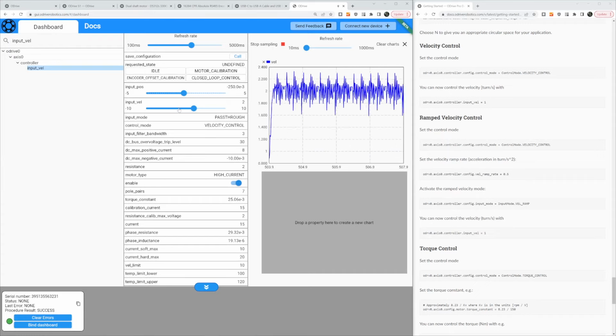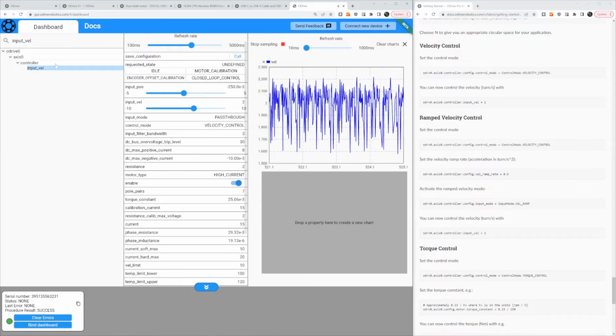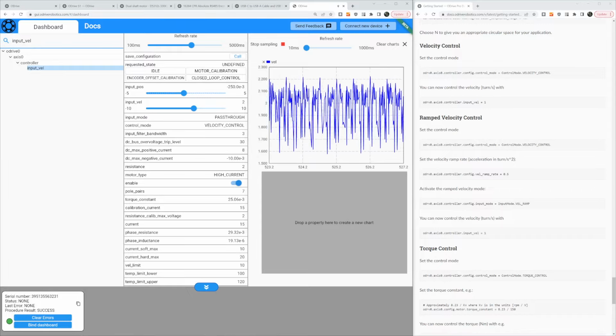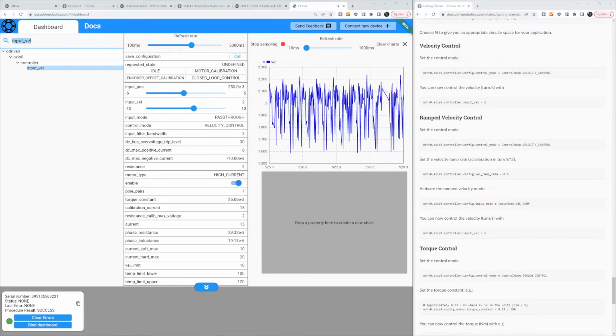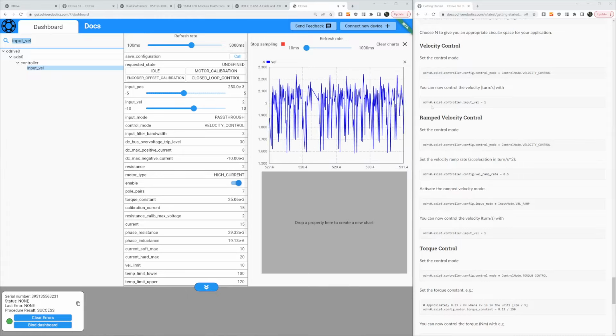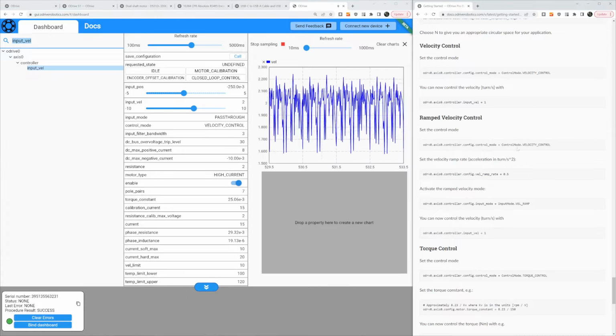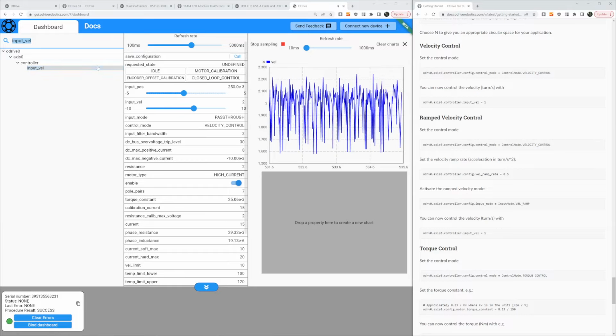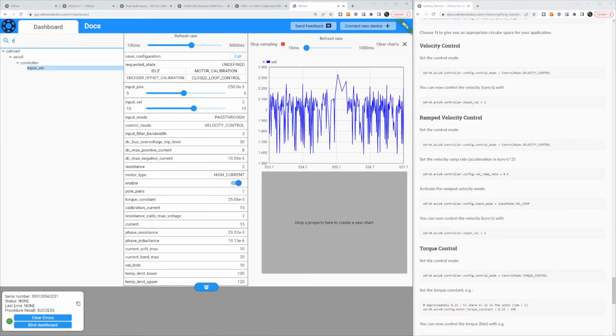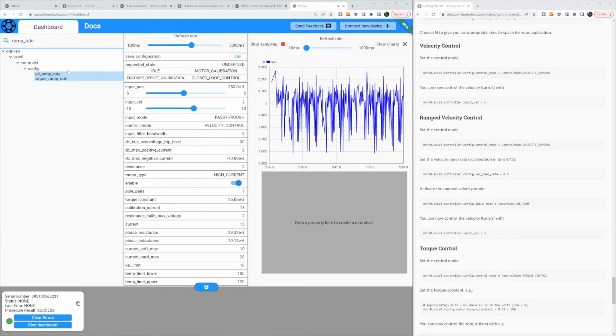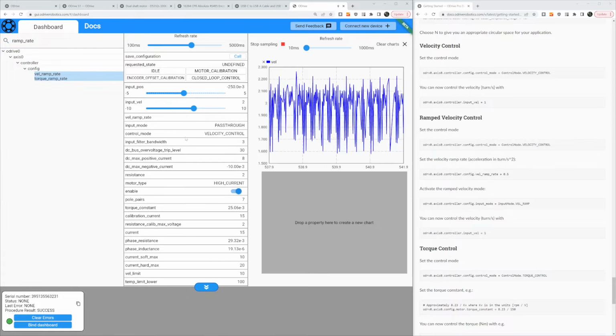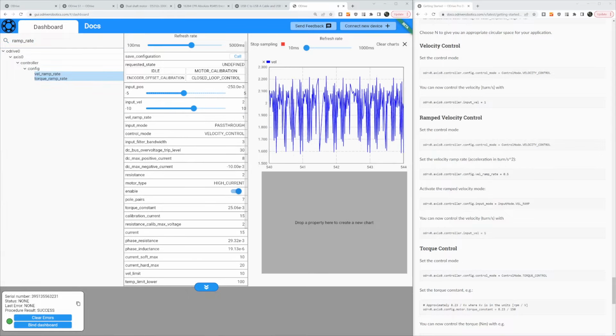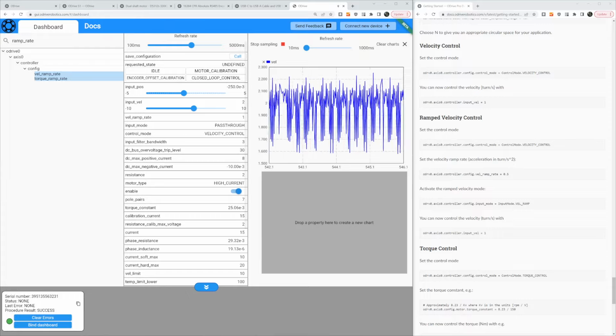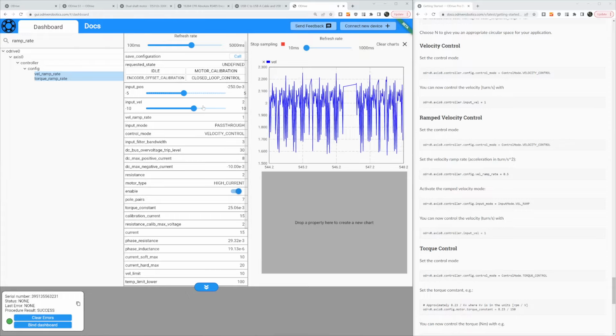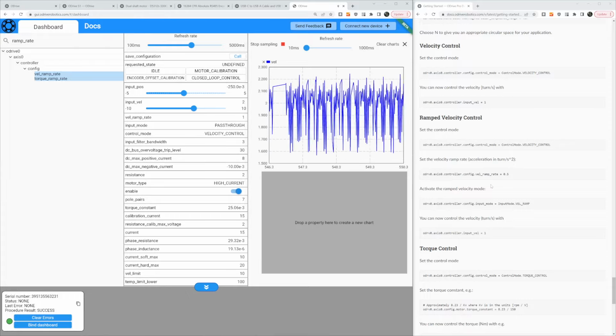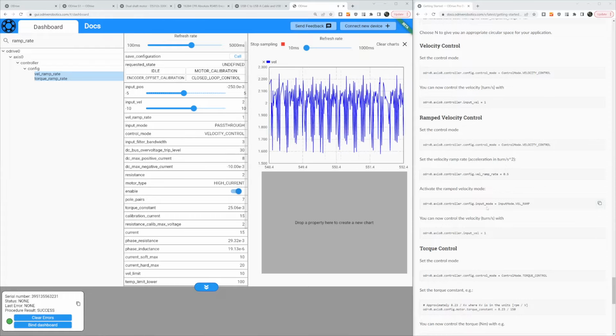So what we can do is use ramp velocity control, which will smoothly ramp it to the target. Let's do that—we have the control modes, velocity control, that's unchanged. We'll set up our ramp rate: the vel ramp rate, 1 turn per second per second. That's quite slow—we can start with that and turn it up after we've seen it work correctly.